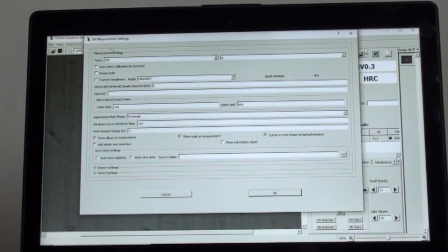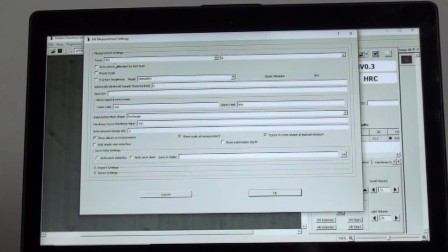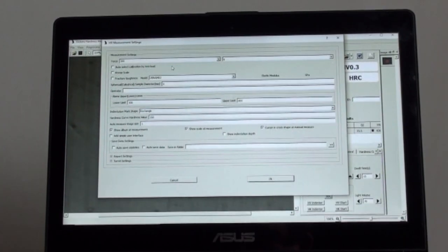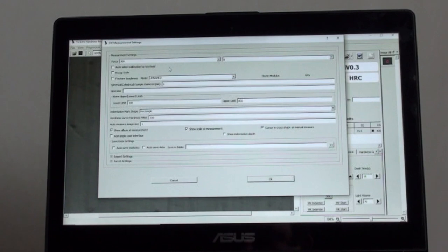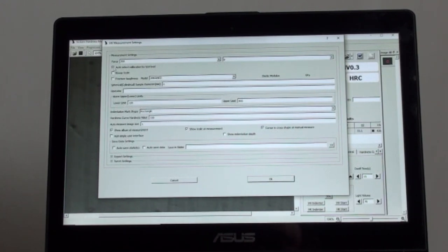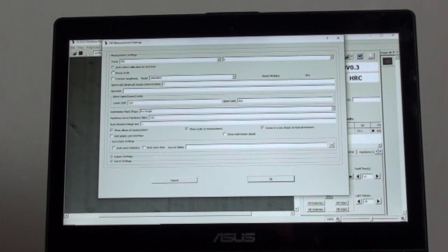The test blocks that come with the machine have suggested weight loads to use. If you intend to do Knoop scale testing, the check box must be marked here and your penetrator must be swapped from Vickers style to Knoop if you don't have a multi-penetrator turret. You can set upper and lower test limits, reporting format and others from the screen.